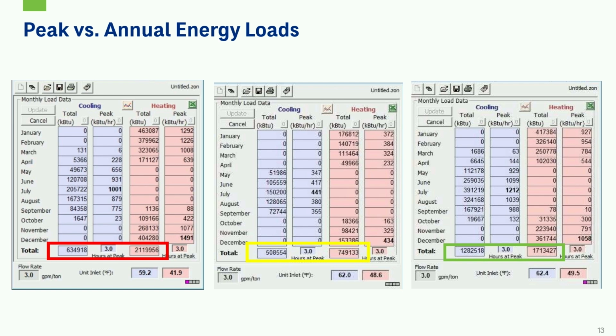So up here, you can see that we have 3 different GLD runs for 3 different buildings with different load profiles. On the far left, we have one building where, if you're just looking at the peak loads, there's a cooling peak load in these blue columns of 1,000 kBTUs per hour in July. And then looking at the heating load, it's somewhat similar with 1,400 kBTUs in December. So just looking at those, I would think, okay, maybe we have a good shot at being a balanced system. But then if you look down at the total, this is our total annual load in kBTUs. We have only 630,000 kBTUs of cooling annually, and then we have over 2 million kBTUs of heating annually. So we have more than 3 times our heating load than our cooling load, which is significantly imbalanced.